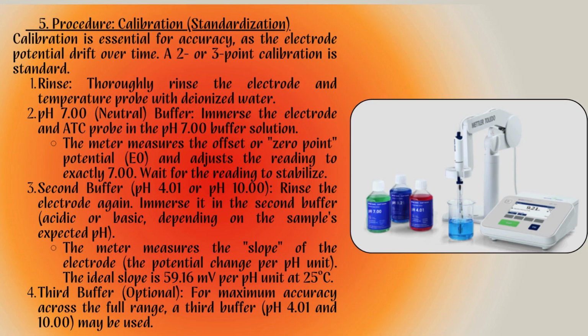The meter measures the voltage at this 0 point and adjusts the reading to exactly 7. This is the offset adjustment. Step 3 is the second buffer. We rinse again and then immerse the probes in a second buffer, typically pH 4.01 for acidic samples or pH 10 for basic samples. This step measures the slope of the electrodes, how much the voltage changes per pH unit. This ensures the meter responds correctly across the pH range.